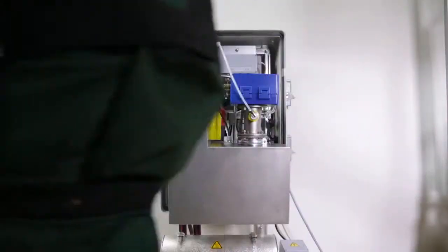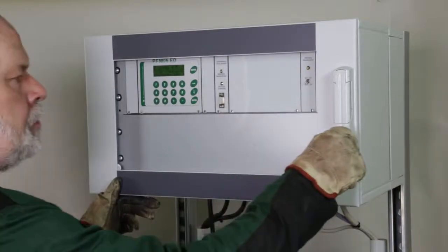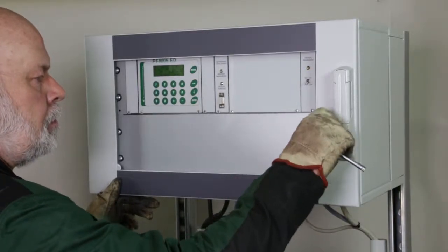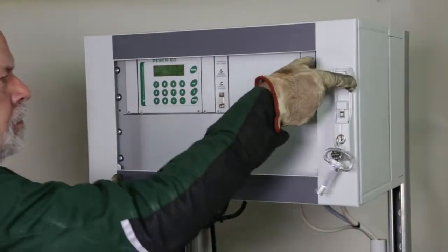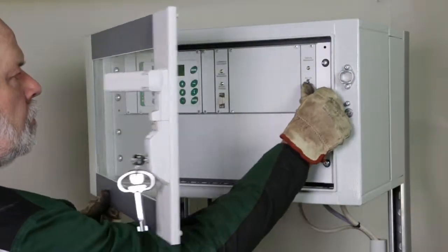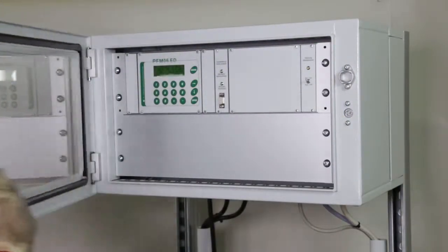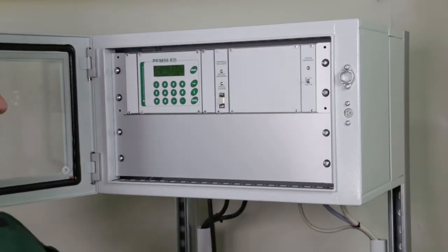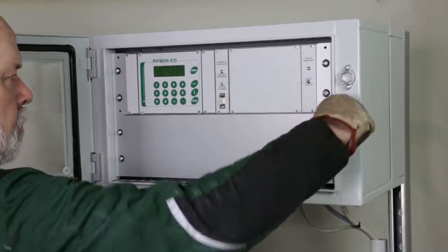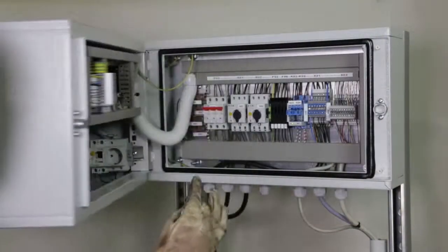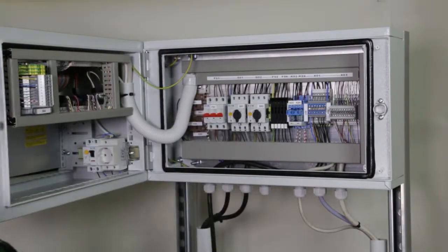For a long-term and stable operation, it is necessary to maintain the measuring system regularly. Check the values for plausibility monthly. Readjust the flows if necessary. Check and clean or change the filters of the blowers and the sampling probe ventilation regularly. Clean the sampling probe every 3 to 6 months.